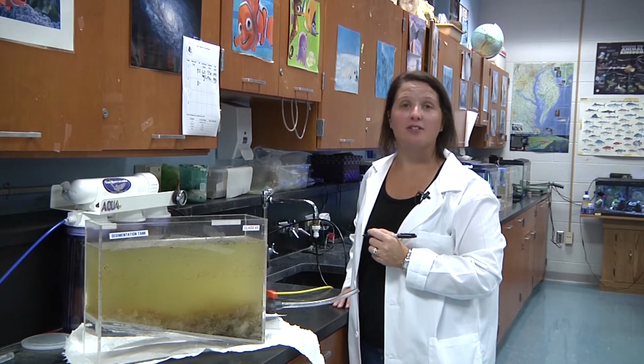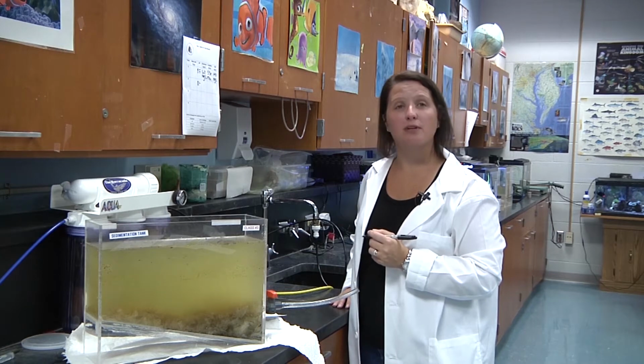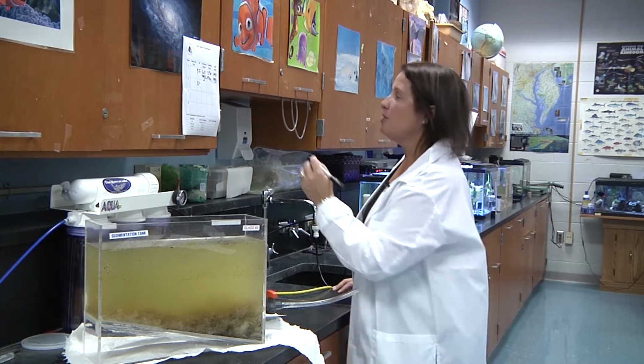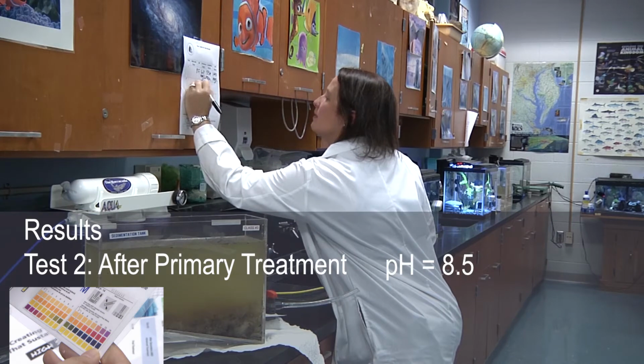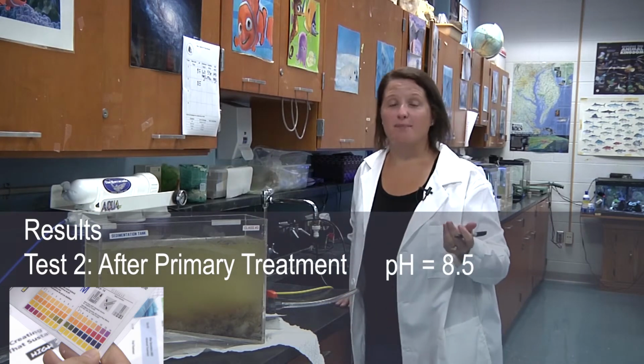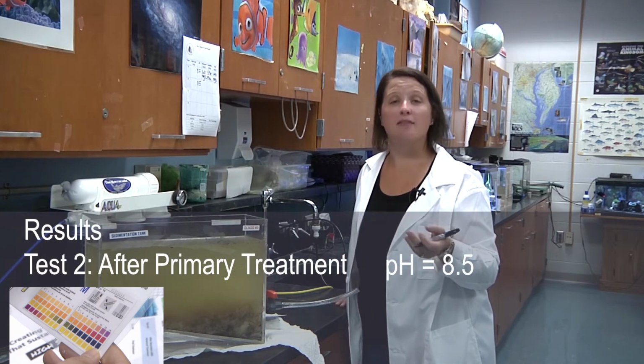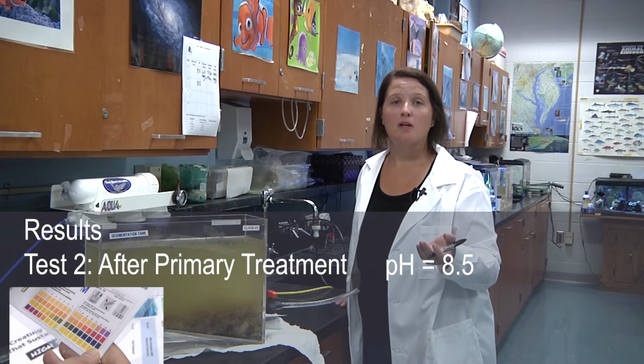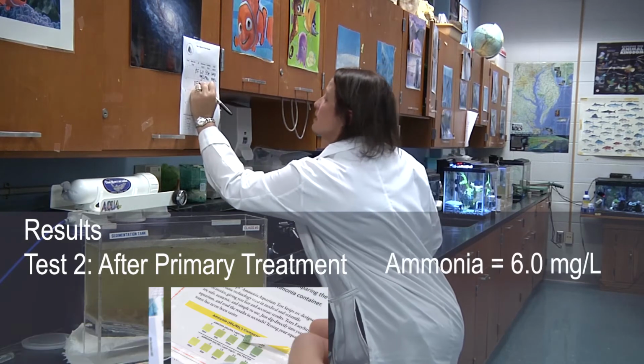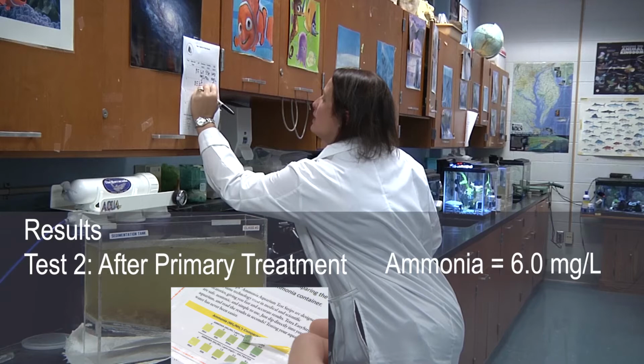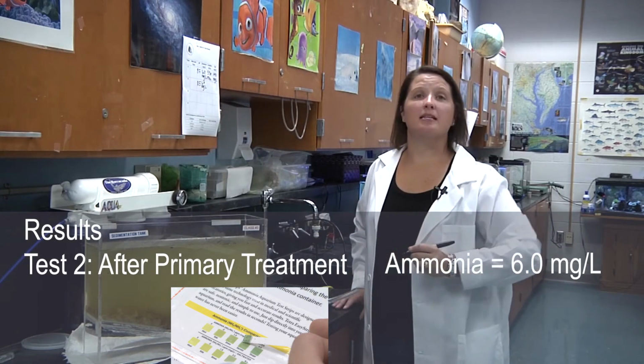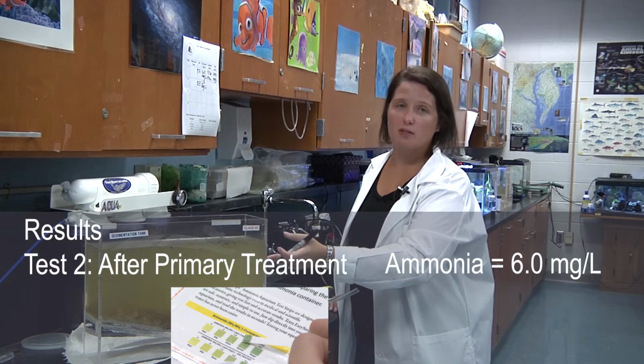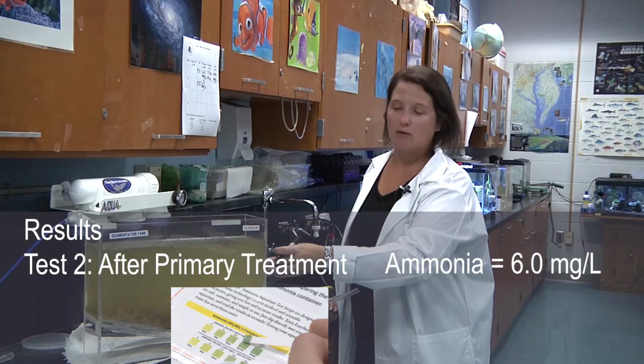Let's look at our data for test 2 and see if the results are reasonable. The pH is 8.5. It stayed the same. We didn't do anything to the tank that would change the pH. Ammonia, 6.0 milligrams per liter. It also remained the same. Ammonia is dissolved in this wastewater, so it won't settle out like bulk trash.